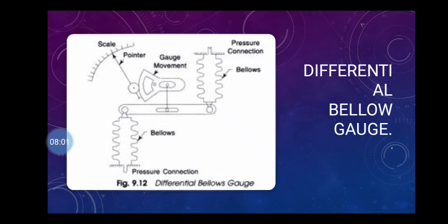Now the question is, what is the advantages of bellows? First of all, it's not a costly, suitable for a low medium pressure range, adaptable to absolute and a differential pressure, capacity to deliver a high force.